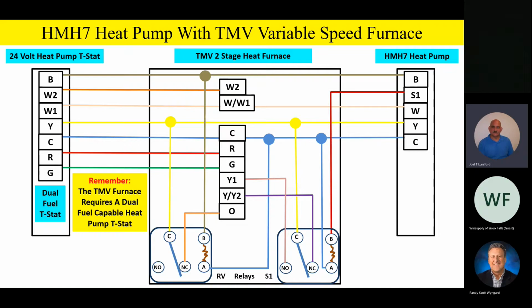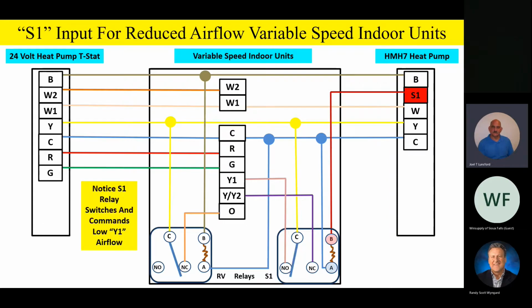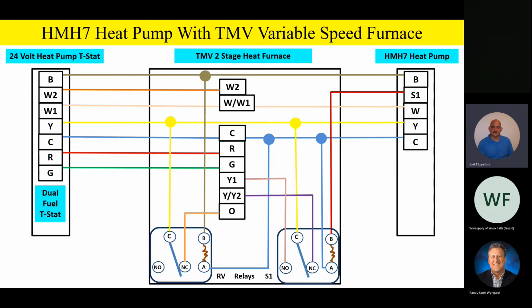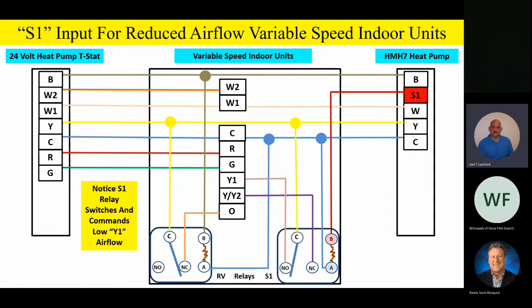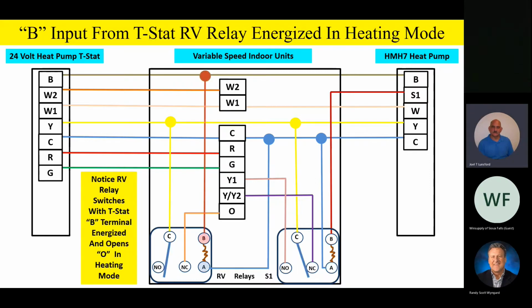So let's go ahead and do some animations real quick. Let's have some airflow reduction on this unit, whether it's a furnace or an air handler. On any of the variable speed indoor units, when we want to reduce airflow, bang, just like we did before, we generate that S1 call outside. It switches the S1 relay and we command that reduced airflow when the outdoor unit is in reduced capacity. But now hang on a second, watch the animation on the left-hand side, the RV relay. When we go into the heating mode of operation and we energize the B terminal, bang, we're going to energize the RV relay and break the O signal by that relay.